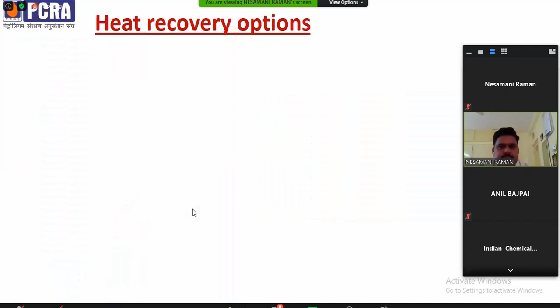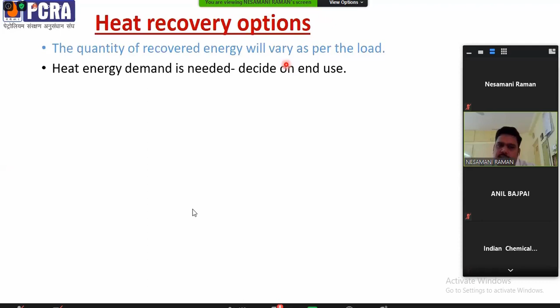We will discuss the circuit diagram, but before that, what are the options? What are the constraints in that? The quantity of heat recovered will vary as per the load. If the loading of the compressor reduces, the heat recovery will also come down. Before finalizing a heat recovery plan, we have to find the demand. Whether we need boiler feed water or any other demand for a cooling system. Do we have a constant demand for heat? Then only we can install this heat recovery option.